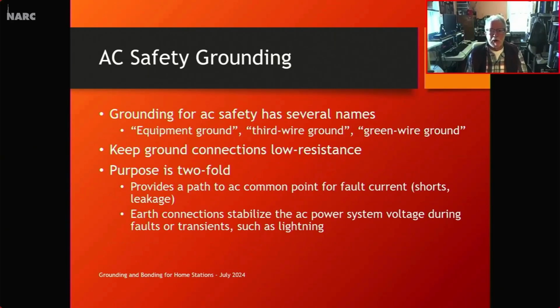And the purpose, there are two purposes for these conductors. One is a path back to your AC common point for fault currents, such as short circuits and leakage. And the conductor has to be heavy enough so that when there is a fault, it can conduct all of the current the circuit can provide, and that will cause your protective components like fuses or circuit breakers to open up and remove power from the circuit, and that prevents shock hazards and fires.